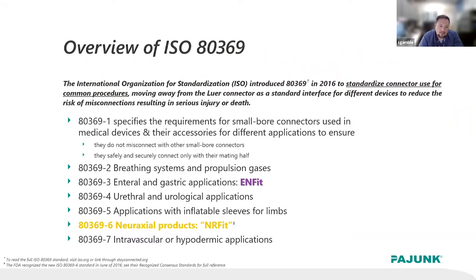Now, what is the ISO? It's the International Organization for Standardization, and it introduced this ruling of 80369 back in 2016 to standardize connector use for common procedures and to move away from the Luer connector as a standard interface for different devices to reduce the risk of misconnection resulting in serious injury or death. And so as you can see, they've basically looked at making it mandatory, or at least the best recommendation from a patient safety standpoint, to change the connection size between all of these different systems and areas to prevent accidental misconnection. For example, you may have heard about the enteral and gastric application ENFit. ENFit was designed and mandated to prevent the misconnection of gastric feeds, for example, to an intravenous connection, which has happened.